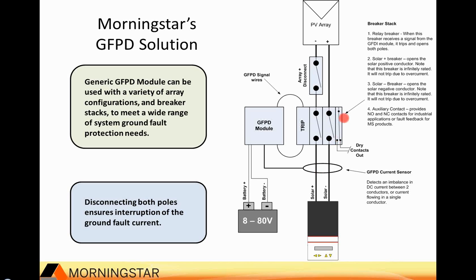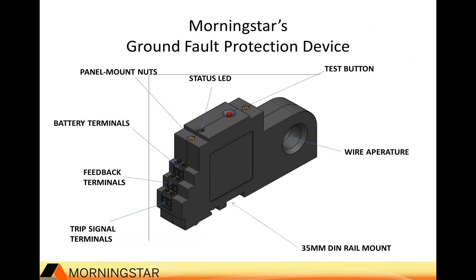Okay, we actually break both the positive and negative of the system. Okay, this is our current measurement device. This is the electronics that power the system, and then it's used with additional breaker stacks to actually perform the disconnect. Okay, so this wire aperture is where you would actually wire the positive and negative, and it would actually detect the ground fault through an imbalance at that location.